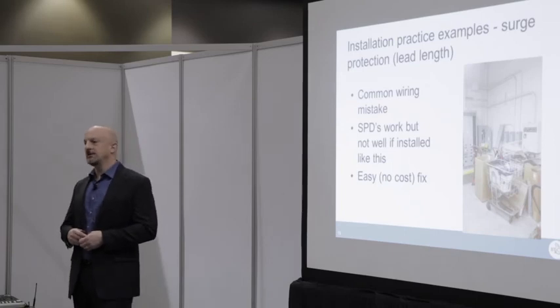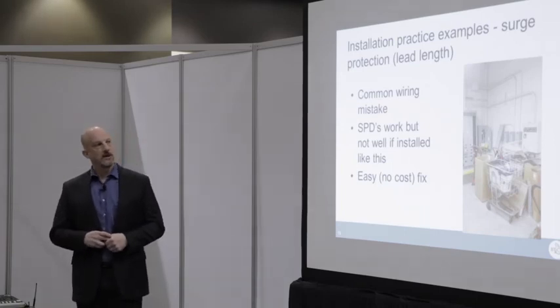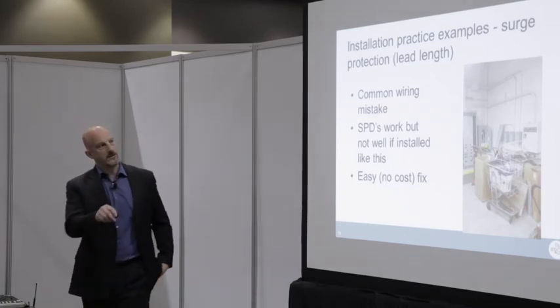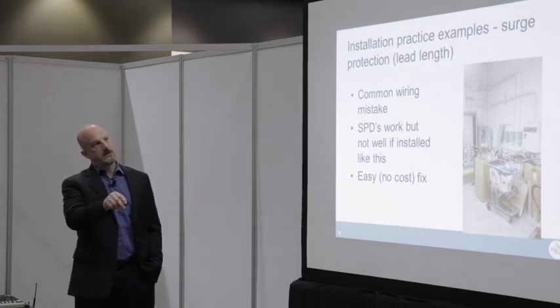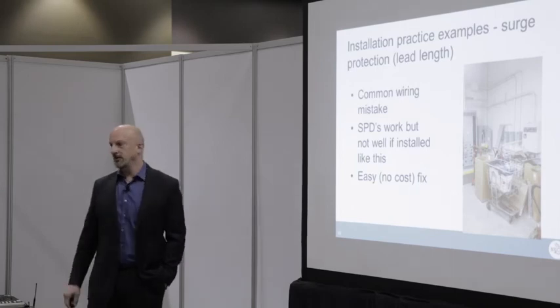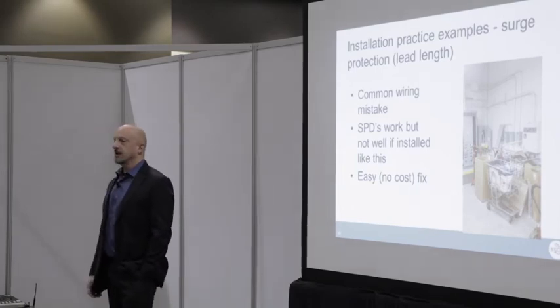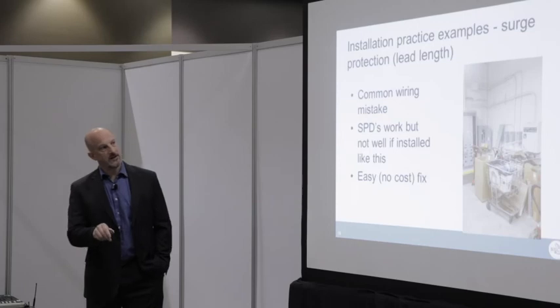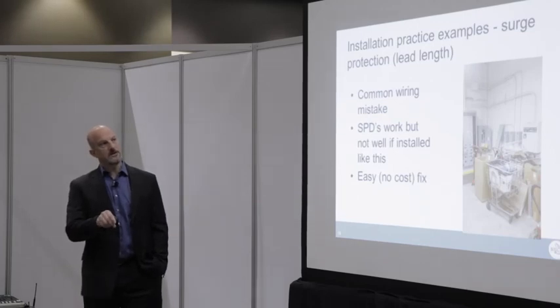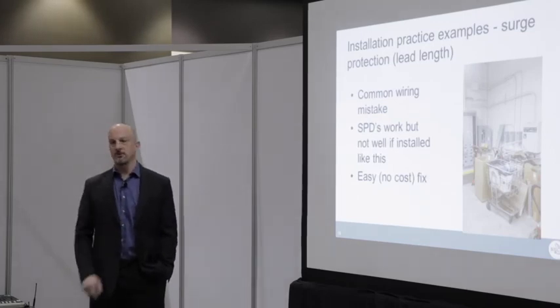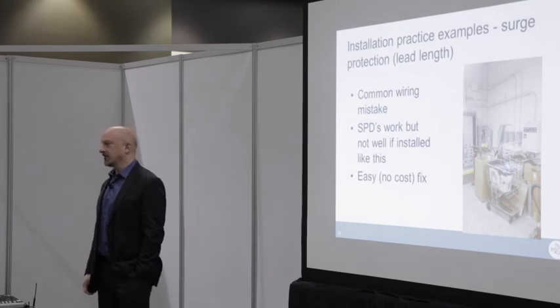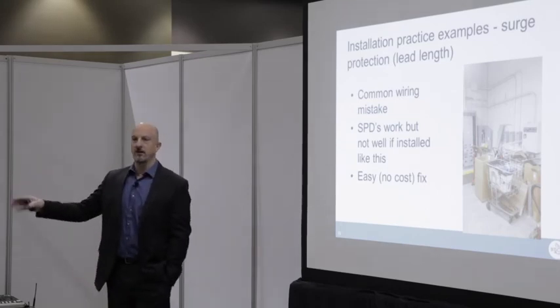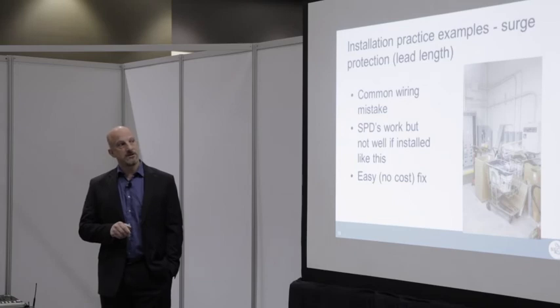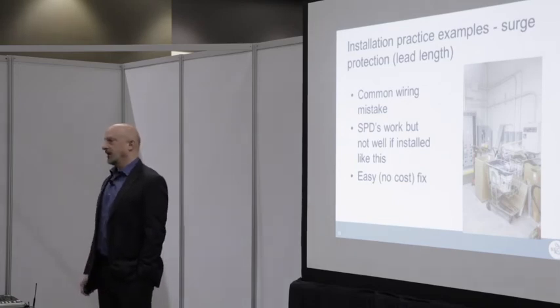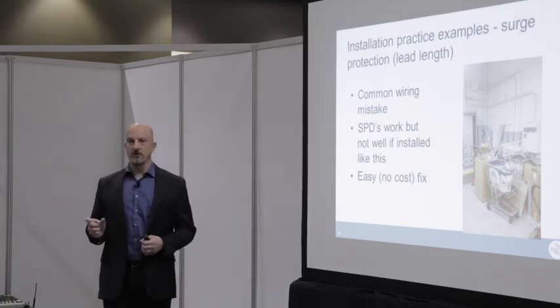One of the most common things we talk to electricians about is lead length. If this is the surge protector and this is the switchboard it's connected to, that distance might be about 25 or 30 feet. It looks good, and this is probably a $15,000 surge protector—they probably overdid it. But the way they installed it, it's not even going to work. That lead length is really important.